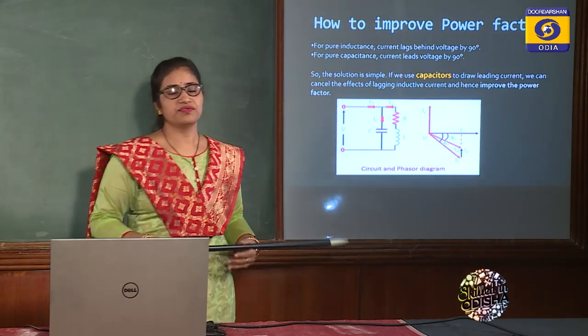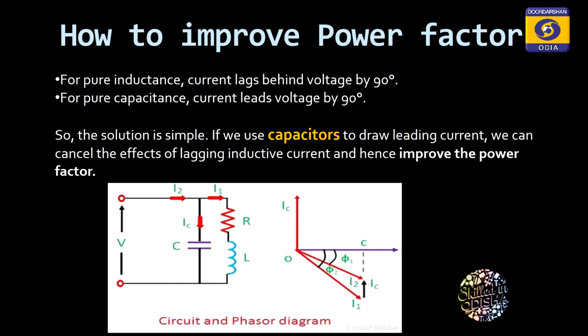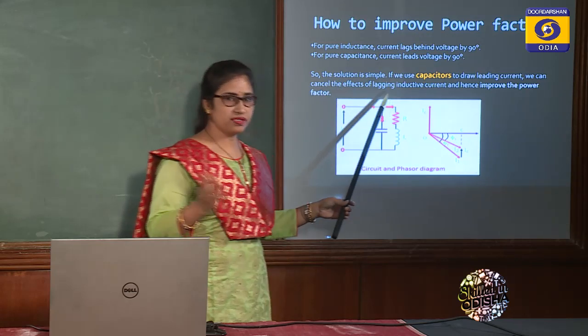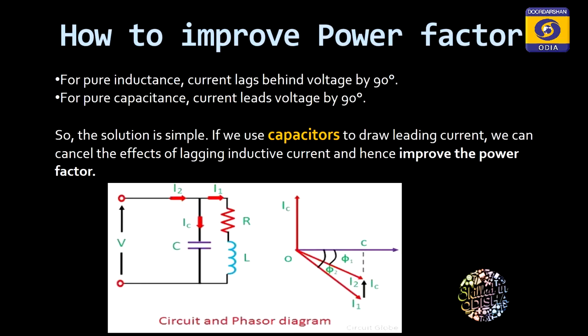So how to improve the power factor? By knowing that inductive loads draw magnetizing lagging current, if we do something to increase leading current in the circuit, it will improve the power factor. The basic and simple solution is to use capacitors, because capacitors supply leading current.